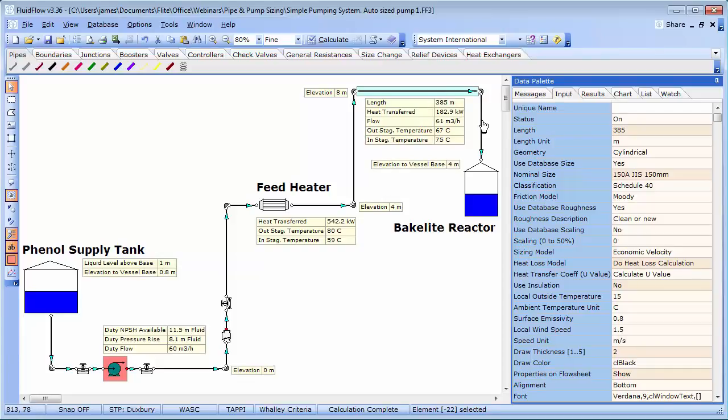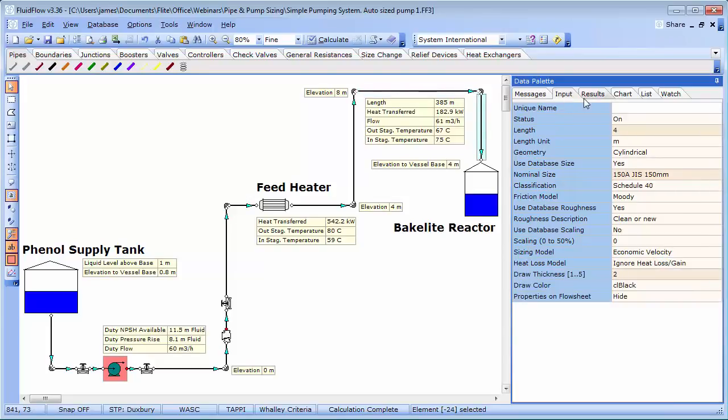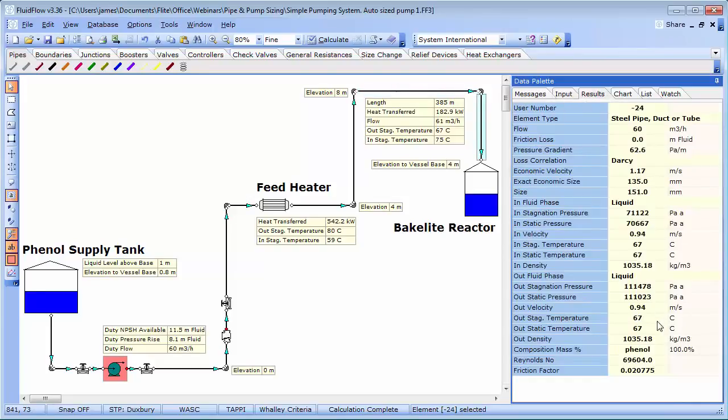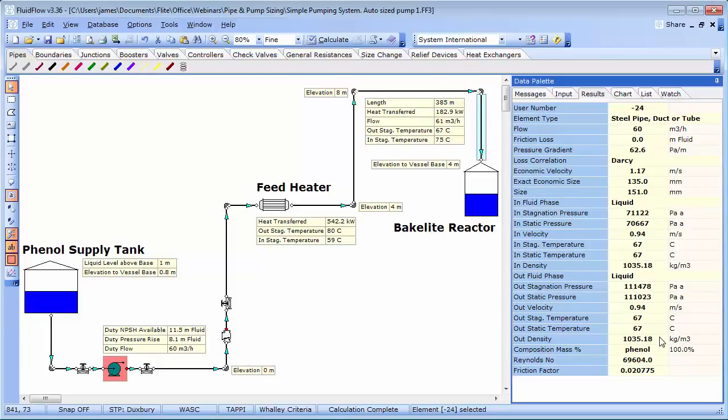The calculation of pipe heat loss takes into account the local ambient temperature, wind speed, surface emissivity, etc. The result is that the temperature of the phenol is just 67 degrees at the supply point to the reactor. We therefore need to consider the inclusion of thermal insulation to the pipe work to minimise this wasteful heat loss, and also for personal protection purposes.